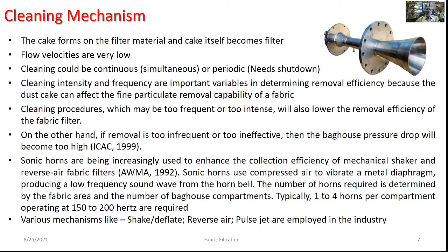For such filters, the flow velocity is expected to be very low. To remove the filter cake, one can use continuous or periodic cleaning mechanisms. Continuous operation can be done simultaneously; periodic cleaning requires plant shutdown. Cleaning intensity and frequency are very important variables in determining removal efficiency, since the dust cake affects fine particulate removal capability. Cleaning procedures that are too frequent or too intense will lower removal efficiency of the fabric filter.